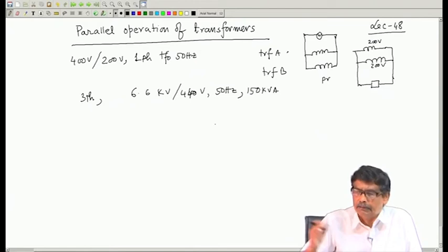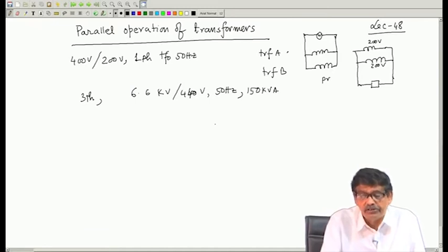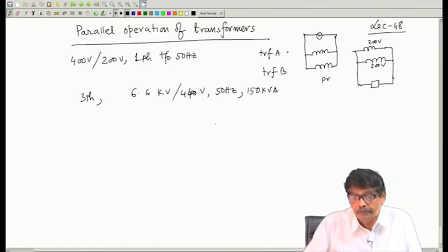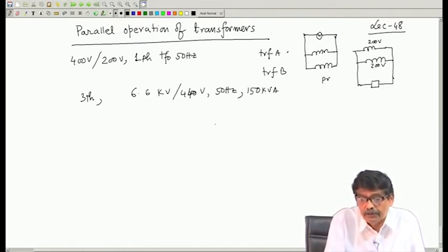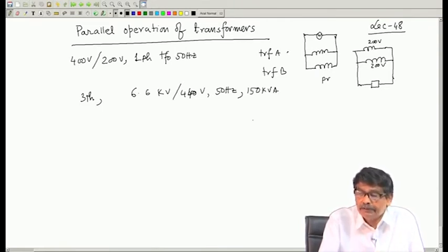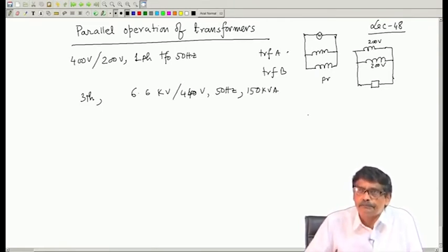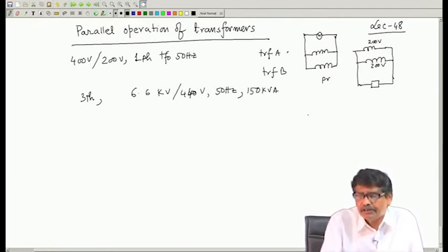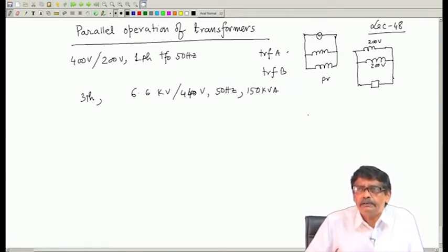Therefore, if the load demand increases, and after 7 years the load demand becomes 300 kVA, what is the option left? Then you have to purchase another transformer of the same voltage rating but 300 kVA, and do away with this transformer, remove this transformer. But that is not an economic proposition, because this transformer is otherwise healthy, and the cost of a 300 kVA transformer with the same voltage ratings is going to be definitely higher.